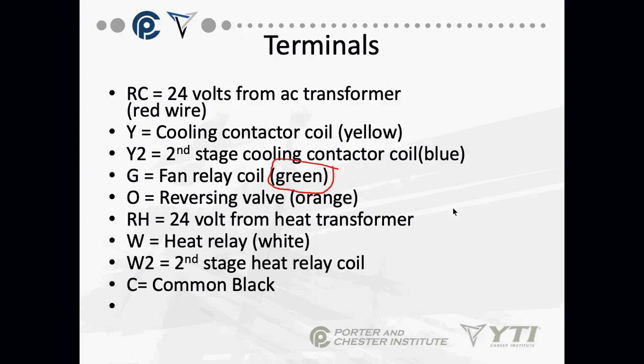The G terminal on a thermostat is for the fan. Thermostats are not grounded. It's low voltage. We don't ground that. So fan relay coil is the G terminal on the thermostat. You've got to remember that. It's important. O goes to a reversing valve. When we're talking a heat pump system, O is a reversing valve. We'll talk more about that in the future. RH, if you have a different system for your heating side, RH is 24 volts from the heating transformer.